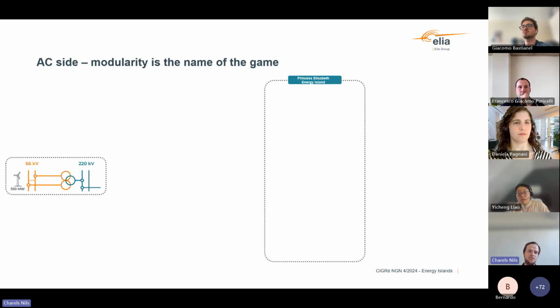It's a connection of wind farm strings with a capacity of about 350 megawatts, connected to our double bus bar 66 kV GIS substation, connected to a three-winding step-up transformer—twice 66 kV windings and a 220 kV winding—then connecting again to a 220 kV GIS substation. That's our building block. We could say, okay, we want 3.5 gigawatts, so we just build ten individual building blocks like this onshore and bring them to the island. But then we'd have a lot of transport to the island and a lot of offshore works as well. So that's not efficient.